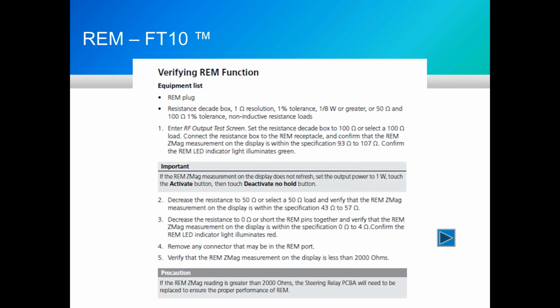And for each one of those, we're going to have to set our resistance value. We're going to have to manually turn on the RF generator and look at what the unit says it sees as a resistance value. When I say the unit, that would be the FT10 generator. So let's start with our first video, and I will add some commentary as the video progresses.